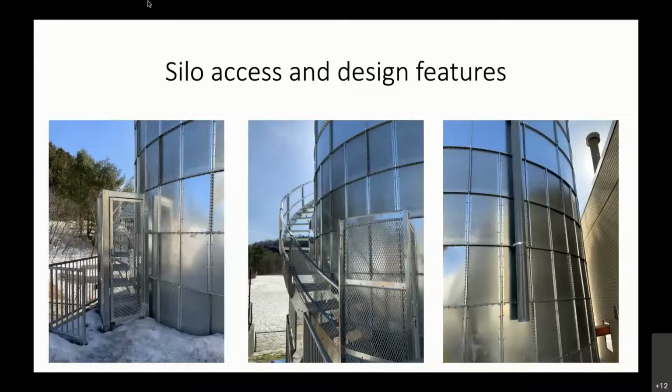The silo design is actually a little bit harder than most people realize. It just looks like a normal farm silo, but in fact, this silo is really picked for many different reasons. We used to use corrugated silos, and we were a little bit unhappy how the additional surface area of the corrugation, in fact, created a lot more friction of our material, and so the flow of the material through a silo was diminished. And so that increased friction coefficient really actually made it harder in the winter months to work. Also, you have a little bit of increased wall surface, so in terms of getting colder, that also made a difference. And so we've seen a lot better performance with these flat wall silos.